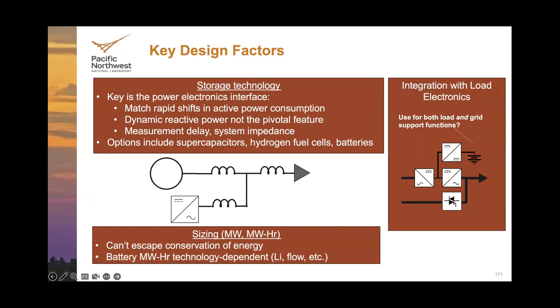We can be clever about sizing, but there's no escaping conservation of energy. If you have a 100 megawatt load fluctuation, that 100 megawatts has to come from somewhere. There's no clever way to control a 10 megawatt battery to deal with that. So there's a lot of thought that this will have to be a 'yes and' solution, where maybe improved GPU-level control gives some attenuation, and you get the rest from batteries or supercapacitors. It's not like you can just slap one thing on and it'll go away.